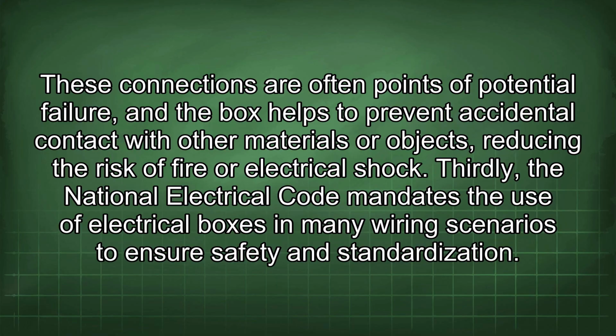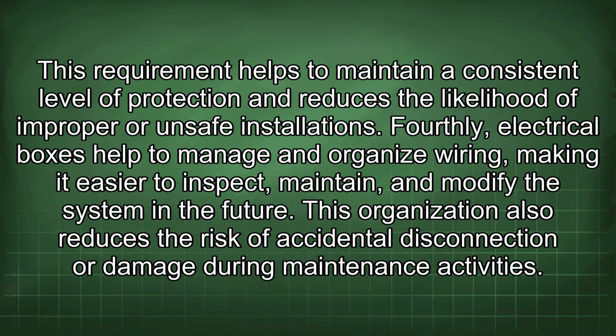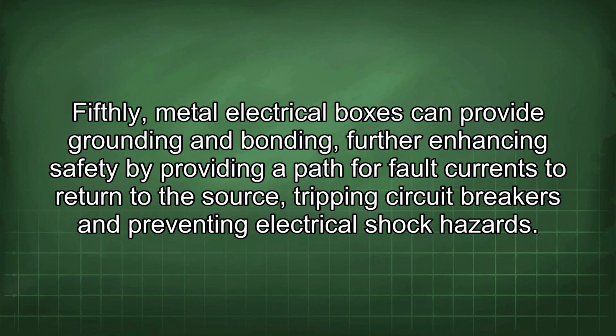Thirdly, the National Electrical Code mandates the use of electrical boxes in many wiring scenarios to ensure safety and standardization. This requirement helps to maintain a consistent level of protection and reduces the likelihood of improper or unsafe installations. Fourthly, electrical boxes help to manage and organize wiring, making it easier to inspect, maintain, and modify the system in the future. This organization also reduces the risk of accidental disconnection or damage during maintenance activities. Fifthly, metal electrical boxes can provide grounding and bonding, further enhancing safety by providing a path for fault currents to return to the source, tripping circuit breakers and preventing electrical shock hazards.